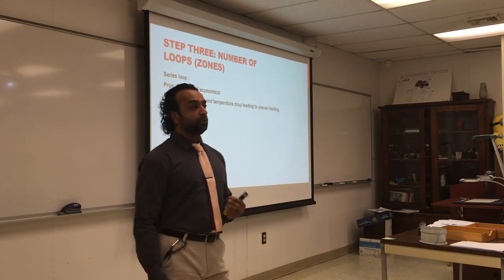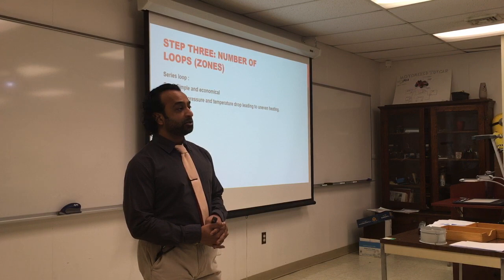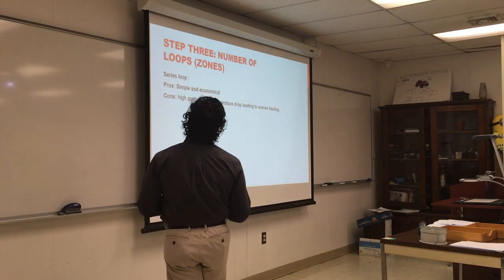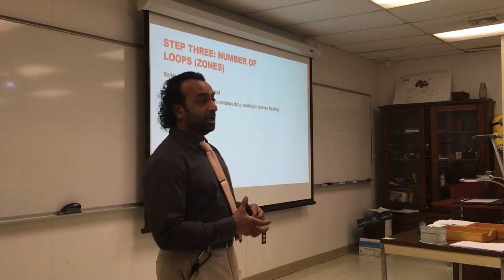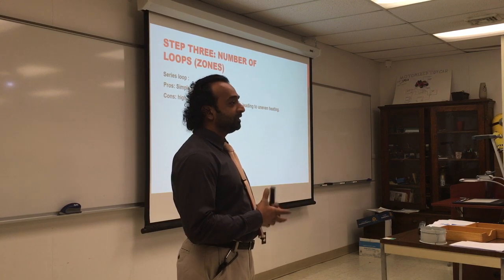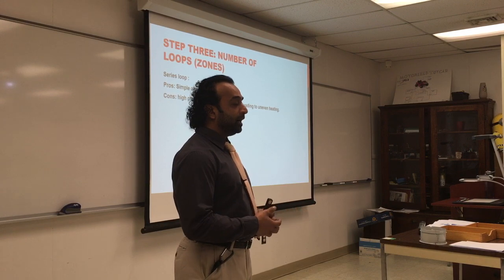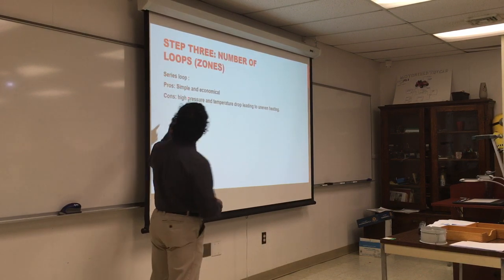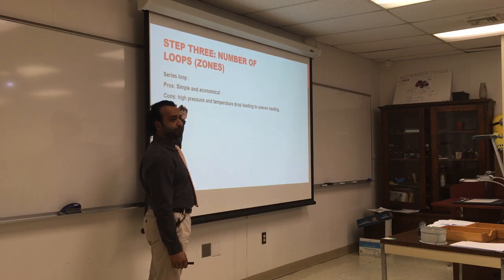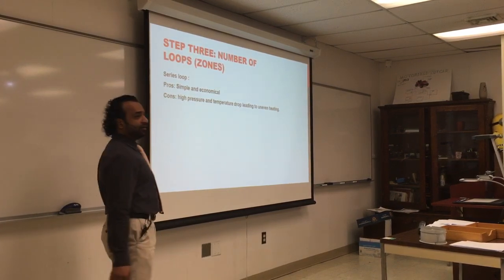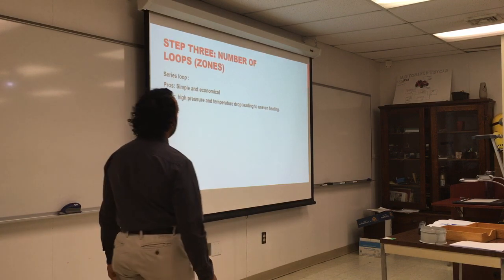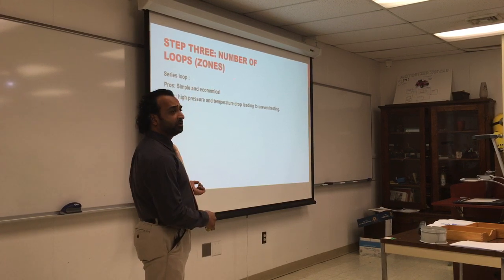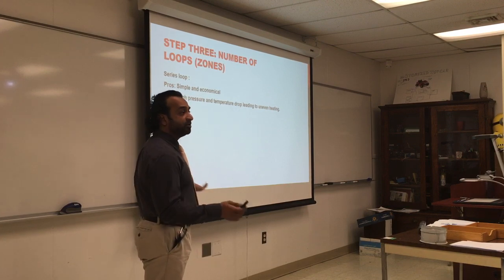Now we look at the boiler loops. Always measure twice, cut once, put a layout, measure it, and have a plot of what you're going to do. For a three-bedroom house, depending on size, you want at least two zones. The more zoning you have, the more efficiency the system will have. A series loop is very simple, very economical, and easy to install, but you will have high pressure losses and temperature drop that lead to uneven heating of the house. It's ideal for a studio, one-bedroom apartment, small loft, or open space.